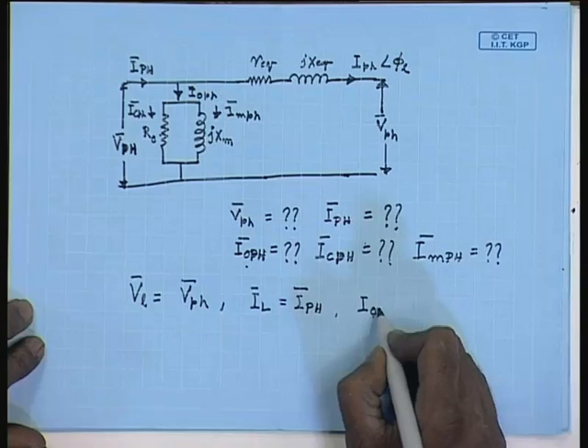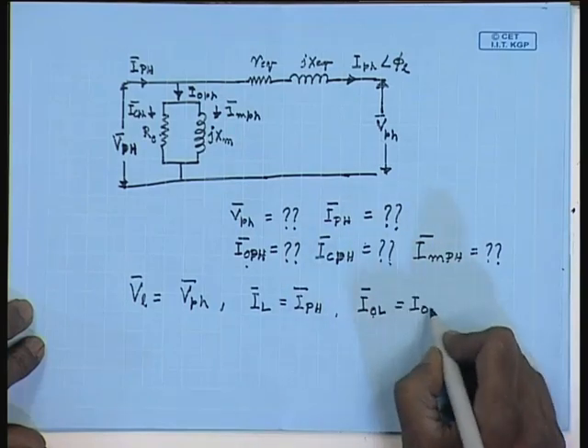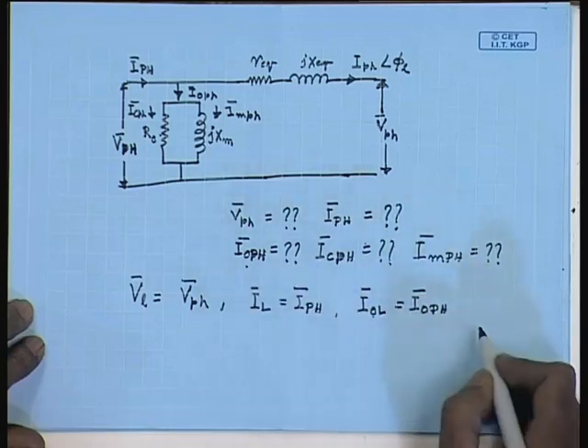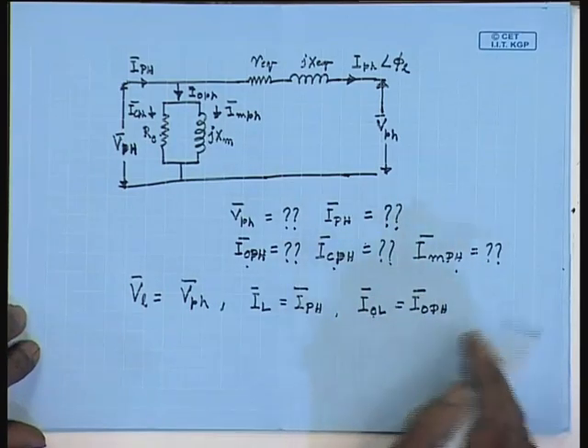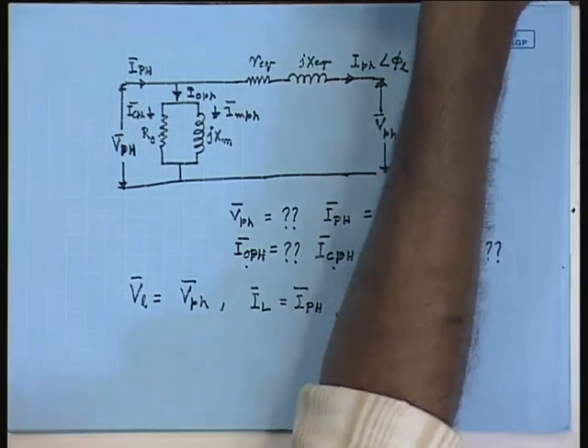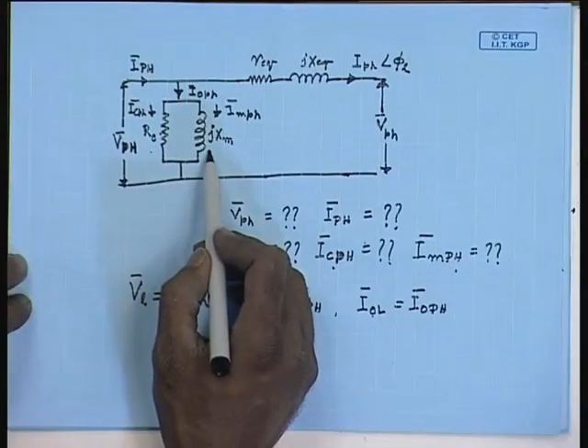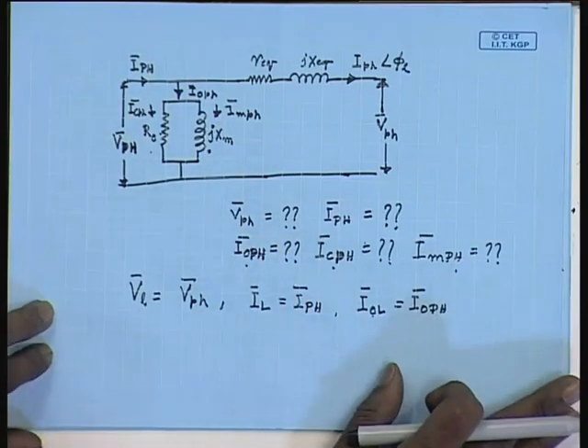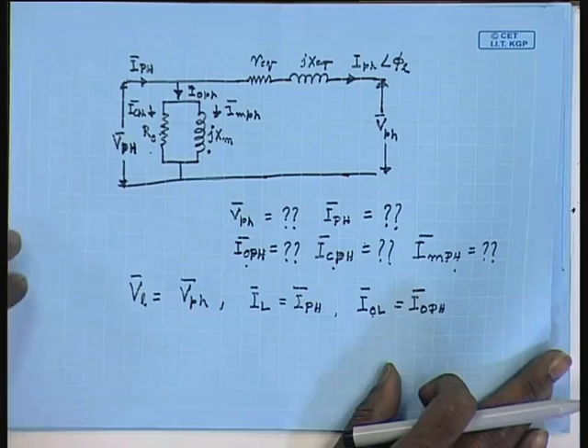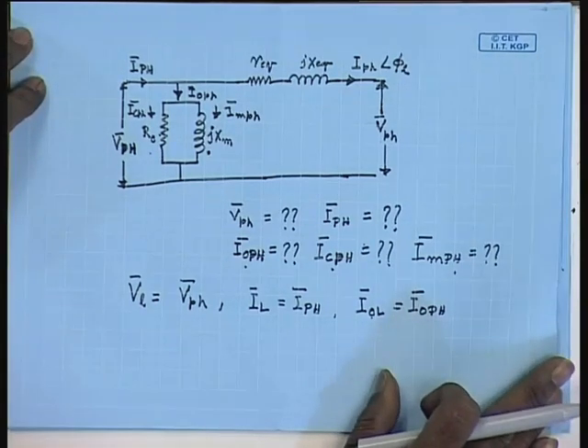So, no load line current referred to the high voltage side will be same as the phase current, and also these two components. So, this is how a 3-phase transformer can be analyzed on per phase basis using the same per phase equivalent circuit as that of a single phase transformer. Now, in order to analyze a transformer using this equivalent circuit, we need to know the parameters of the equivalent circuit, and in order to find these parameters, we performed no load and short circuit tests. The similar tests are to be carried out for 3-phase transformer as well.